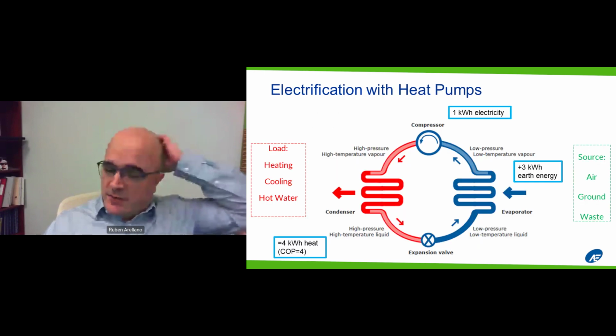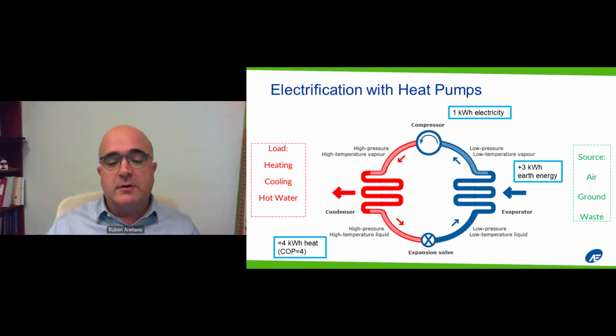There's a lot of talk about decarbonizing our building heating and cooling through electrification, which usually means converting to heat pumps instead of just combustion of fossil fuels or electric resistance heat—not always, but in the majority of applications. A heat pump is a simple mechanical device using the vapor compression refrigeration cycle, enabling the moving of energy from a lower temperature source to a higher temperature source. In this example, our sources might be the air—an air source heat pump—or the ground, a ground source heat pump, geothermal or geoexchange, or even waste heat recovery or wastewater heat recovery.